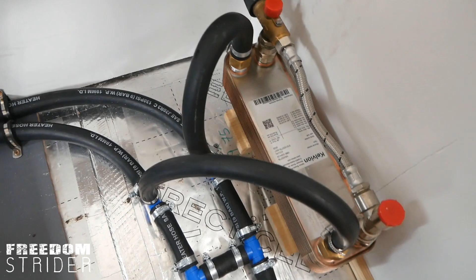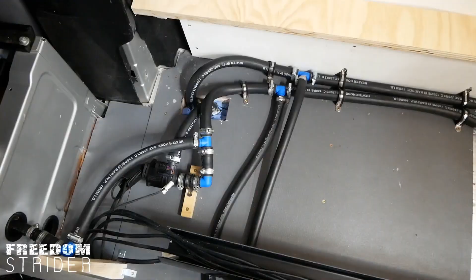Oh, it stopped. So without doing anything else but rearranging the pipes lower down to the ground and taking a quick drive, which moved the glycol about, we managed to prime the pump. We got glycol in the pump, which made it prime itself and start pumping glycol around the system. So that's problem one solved - glycol in the pump. Okay, next.